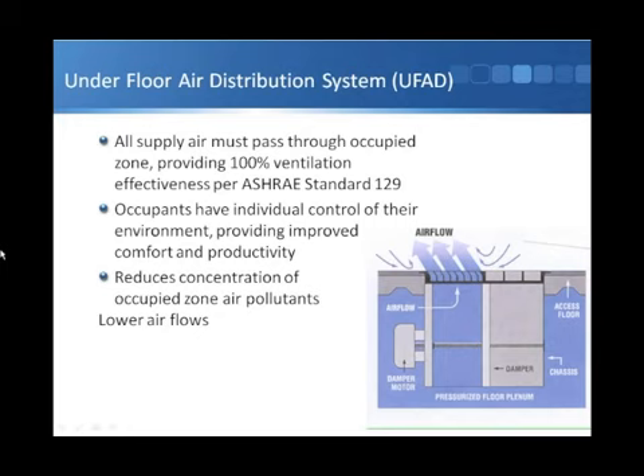For example, controls cabling might go through the floor zone along with all the other cables and data and so forth, but it might then go up a conduit to a thermostat on a wall in the occupied space. And by doing that, it then provides a path for air from the plenum up across the thermostat. So the thermostat is essentially reading the air supply temperature rather than the temperature in the occupied room, and so it's given a misconception of what the room space is, and that's been an issue.